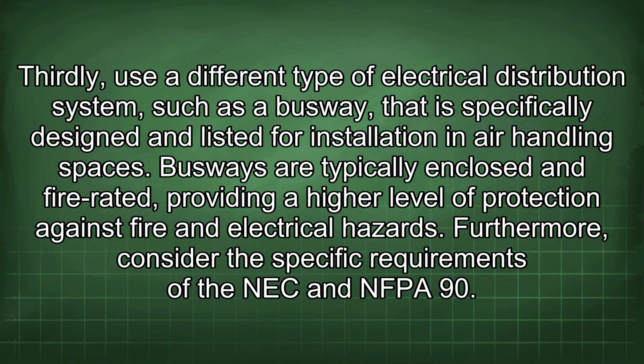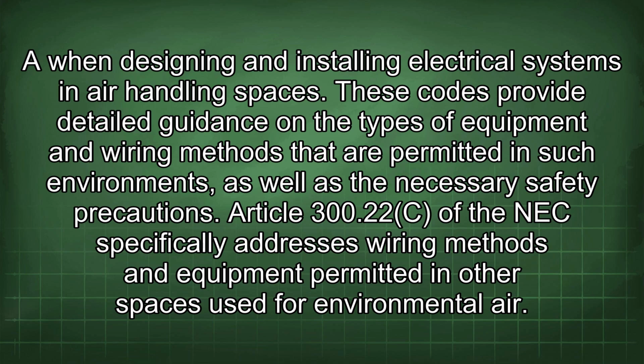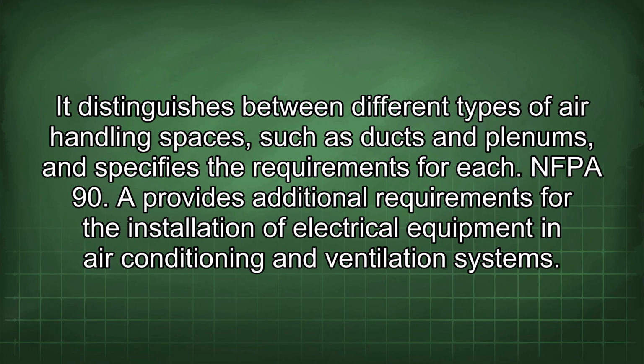Furthermore, consider the specific requirements of the NEC and NFPA 90 when designing and installing electrical systems in air handling spaces. These codes provide detailed guidance on the types of equipment and wiring methods that are permitted in such environments, as well as the necessary safety precautions. Article 300.22(C) of the NEC specifically addresses wiring methods and equipment permitted in other spaces used for environmental air. It distinguishes between different types of air handling spaces, such as ducts and plenums, and specifies the requirements for each.